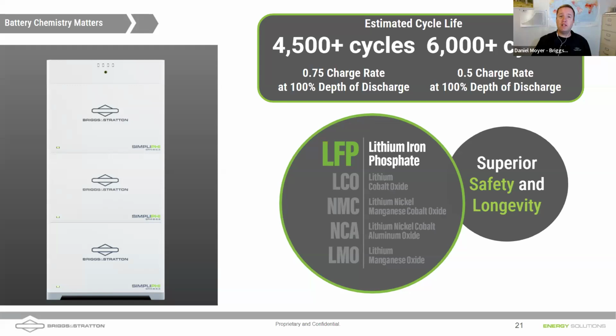Yeah, exactly. And so we're able to utilize the full capacity, although we still maybe recommend maybe a 90% DOD before hitting that low battery cutout voltage. But absolutely, we can get 6,000 cycles. If you're cycling that daily, that's something like 16 years. And that is at 100% depth of discharge, at over C over 2 rate.